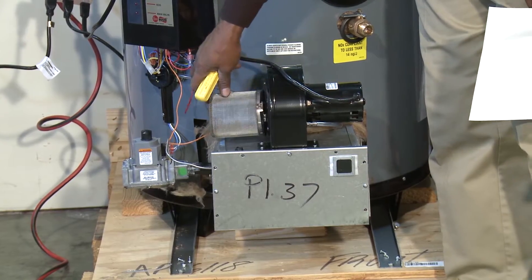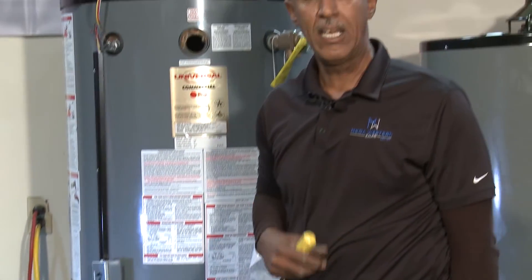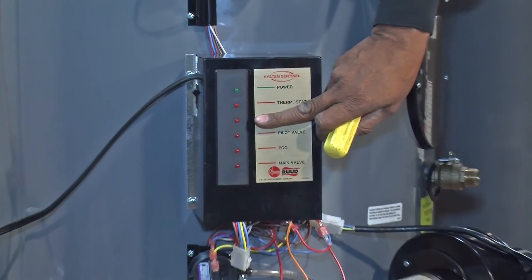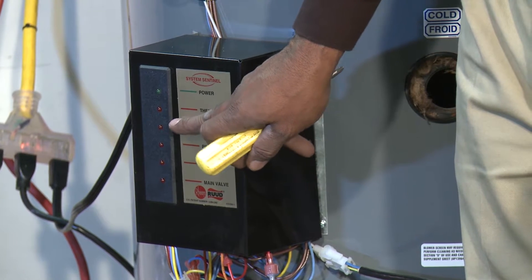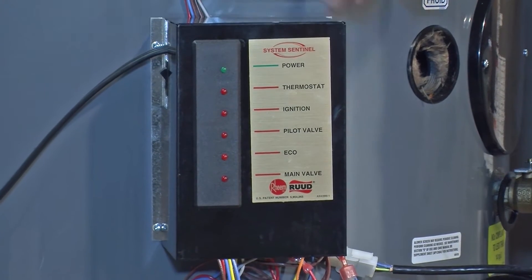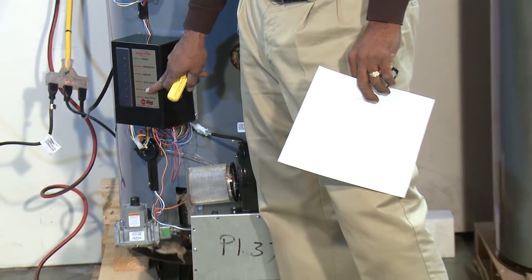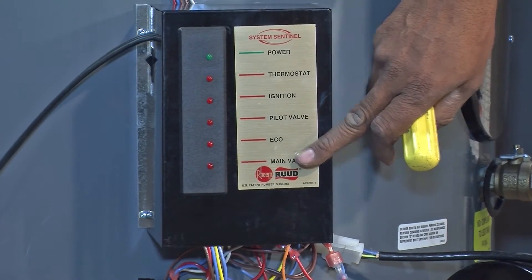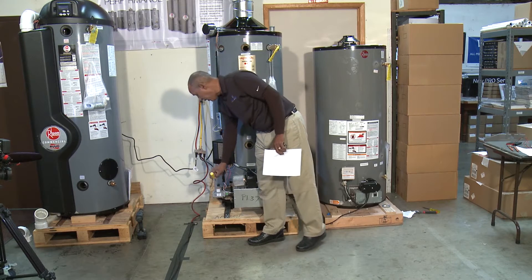That is the basic maintenance this water heater requires. Like most commercial water heaters, this unit is technically self-diagnosing. It has what we call a System Sentinel on the control box. Each light indicates where the water heater is in its operating and firing sequence. If it stops at thermostat, there's something wrong with the thermostat; if at ignition, something's wrong with the igniter; if at pilot valve, something's wrong with the gas or pilot valve; if at ECO (the pressure switch located under the unit with a clear tube), there's a problem with the pressure switch; and if the main valve light doesn't come on, there's likely a problem with the main valve.